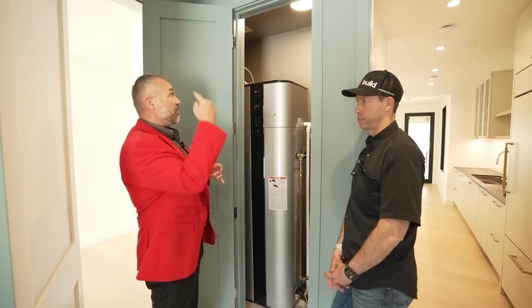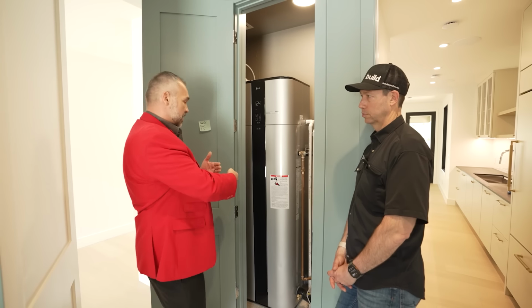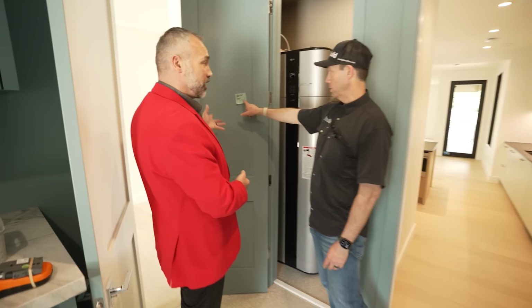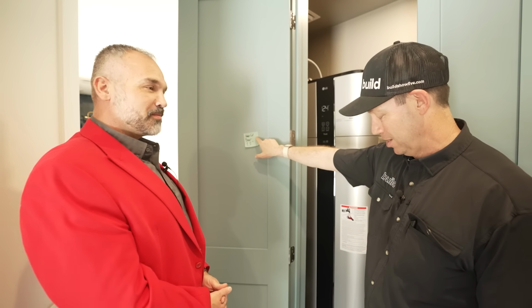So having a little bit of pressurization inside this closet as it operates, and I'm assuming we're going to provide some kind of a passive pathway. I see a note you put on here to undercut the door. I realized that before you came today. Oh shoot, I didn't get my undercut done. So we could actually use ChatGPT to do the math for us to figure out the undercut, but we need enough space that air can pathway out.